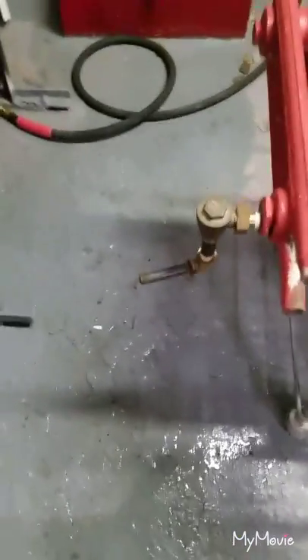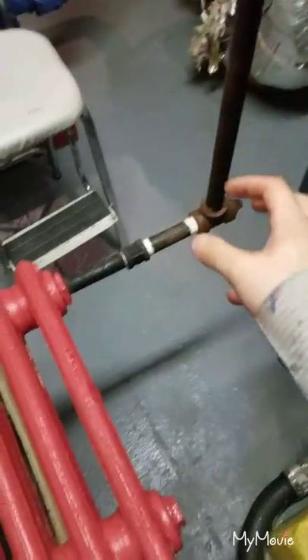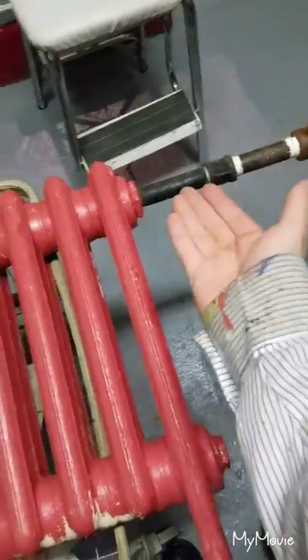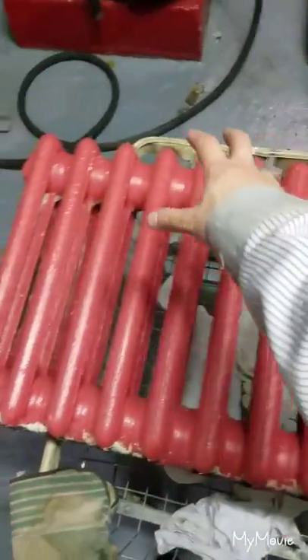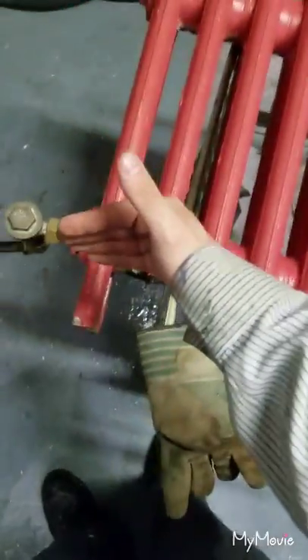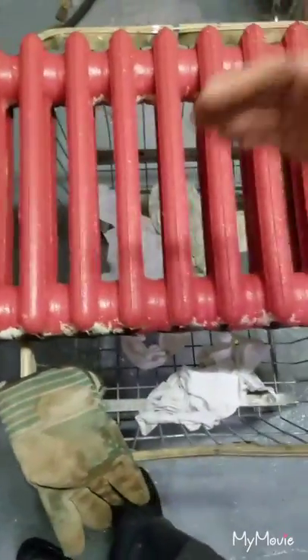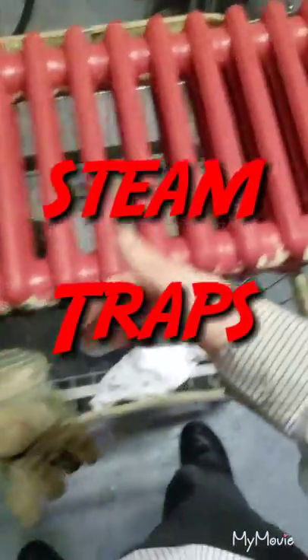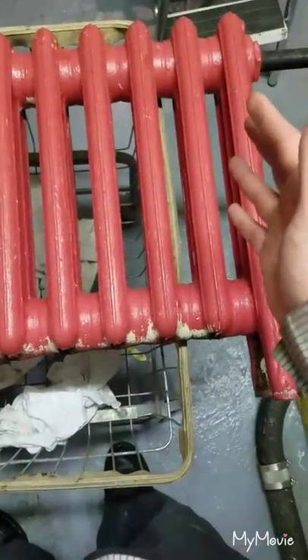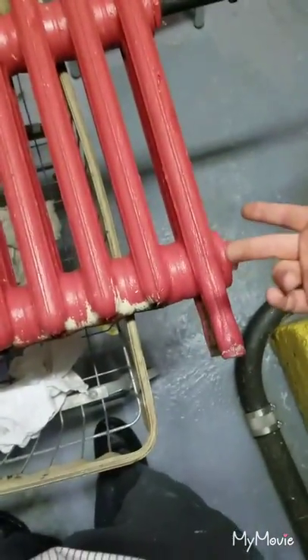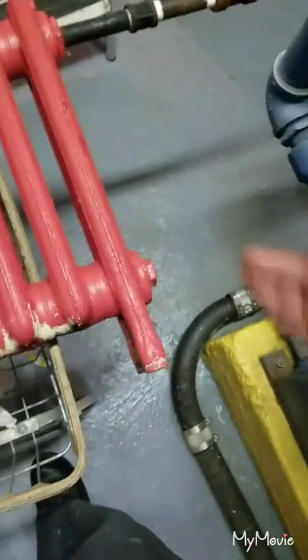So just to give you a little demonstration, this would be the low pressure steam coming from the boiler at 2 to 3 pounds. Steam comes in the top of your radiator through the top header, comes down, fills all these chambers, you can feel the heat, comes this way. Now if it's a one pipe steam heating system, the steam will just fill this radiator, and then when it's done, usually this pipe would be at the bottom and the water would just come back and go down to the boiler.